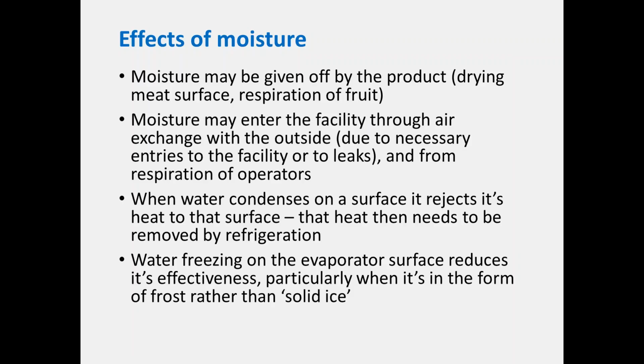Sometimes moisture production is inevitable, as with horticultural products - they respire, and you can't do much about that, apart from modifying the atmosphere so the rate at which they give off moisture is reduced. But there are other factors too, like exchange with the outside air when we load or unload the facility - we can't avoid that. Just recognize it's a very significant load on the compressor, because when moisture condenses on the surface, it has to reject its heat to the product.